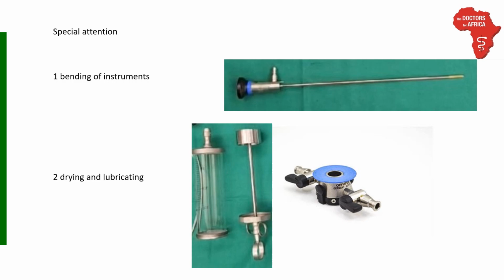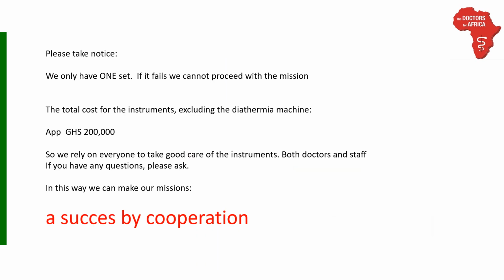At the end of the day, see to it that you dry all instruments and especially the syringe and the plunger. Otherwise, there will be corrosion on the metal part and the plunger will not slide into the glass easily anymore. You might add some silicone oil to it. Please take notice, we only have one set. If it fails, we cannot proceed with the mission. The total cost for the instruments, excluding the diathermia machine, is approximately 200,000 Ghanaian cedis. So we rely on everyone to take good care of the instruments, both doctors and staff.